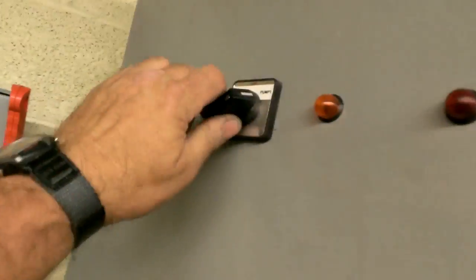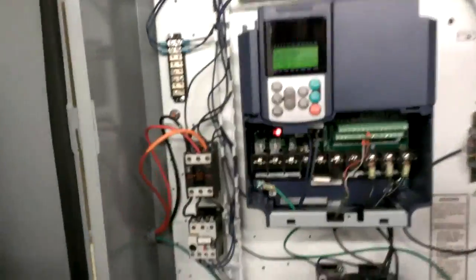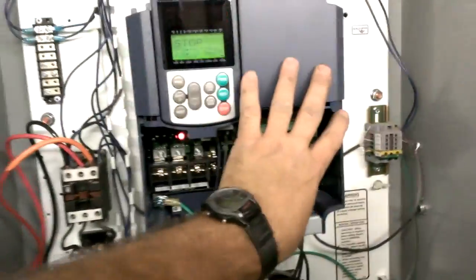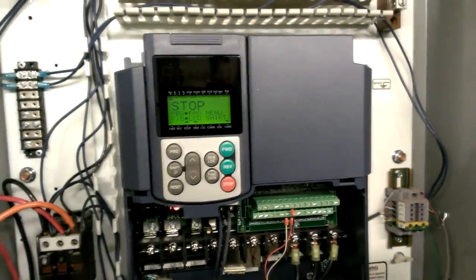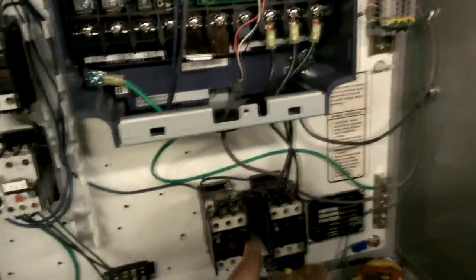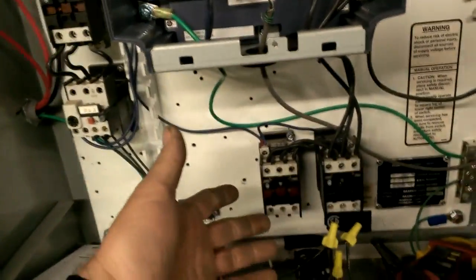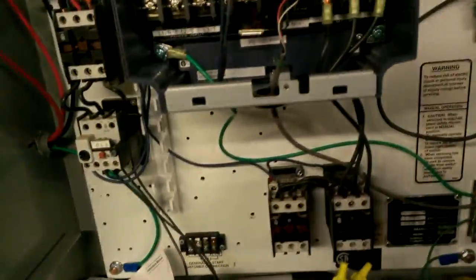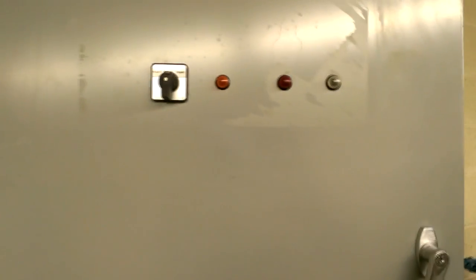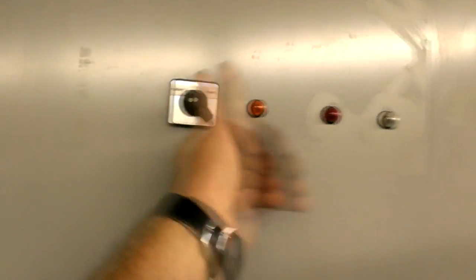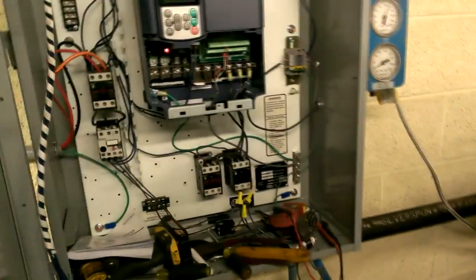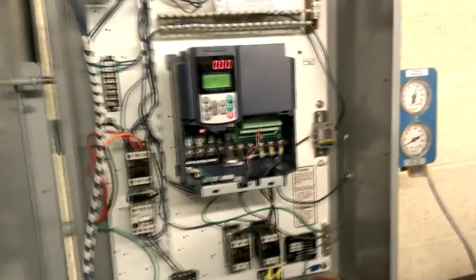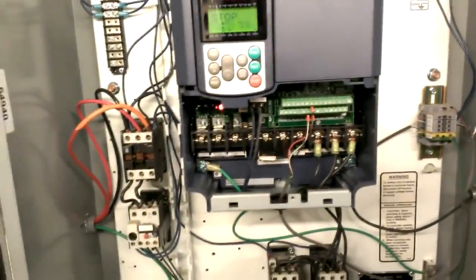If you switch motors, though, like go from one to two, what I wanted to do is the logic will first give the command to stop on the VFD. Then open up the contactor for that motor and then energize the contactor for number two, in this case. And then give the command for the VFD to start back up. That way somebody, I can have regular maintenance guys come in here after hours or whatever. If one pump fails or is noisy I'll be able to just go bam, switch it to the other one. It's not like it's gonna slam when the contactor's open and shut on the output of that VFD. My controller will control switching the contactor while it first stops the VFD.